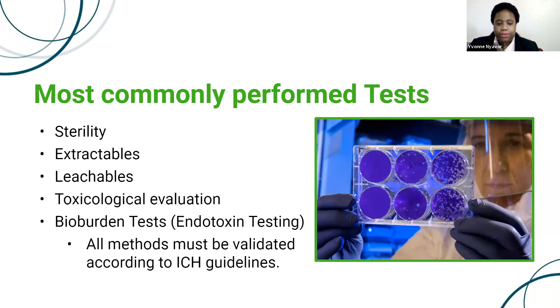So let's kick things off with sterility tests. So why a sterility test, someone might ask? A sterility test is basically to establish that the tested product meets sterility specifications. So what are these specifications, you may ask? Basically, if that product is, for example, a class 3 device, which is high risk, obviously it has to be sterile. We don't want any microbes on it when it's going inside of somebody's heart or brain, which can cause an immune response or result in illness or infection in a patient that typically already has underlying health conditions. So we use a sterility method that is based on USP 71 and ISO 11737-2.